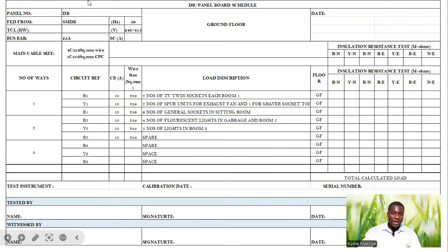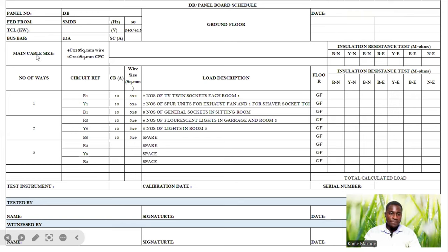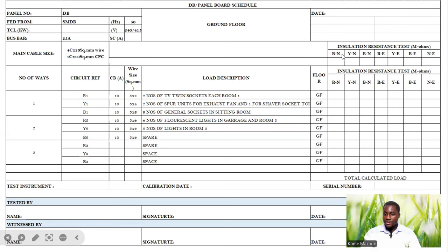As you can see, we have a load schedule which we've prepared. On the other side, we mention the different tests to be carried out — the insulation resistance tests. We have our main cable size, which is a four-core 10mm² cable, and the earth conductor which is also 10mm². We conduct our test between phase and neutral: R and N, Y and N, B and N, R and E, Y and E, B and E, and neutral and earth.